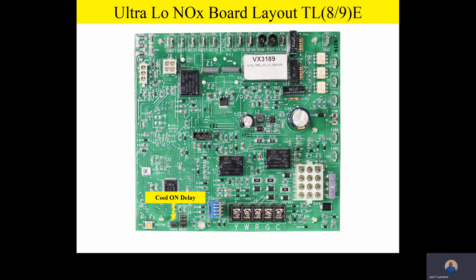Right next to the cooling on delay jumper, we have a SW1 fault recall switch. What this does is allow the technician to recall any faults on the board. So by depressing the fault recall switch, he'll be able to pull flash codes off the board in its memory. Now, it should be noted the board remembers the last 5 faults. After the 5th fault, it kind of rolls off the end. In other words, it's going to remember just the last 5 current faults.